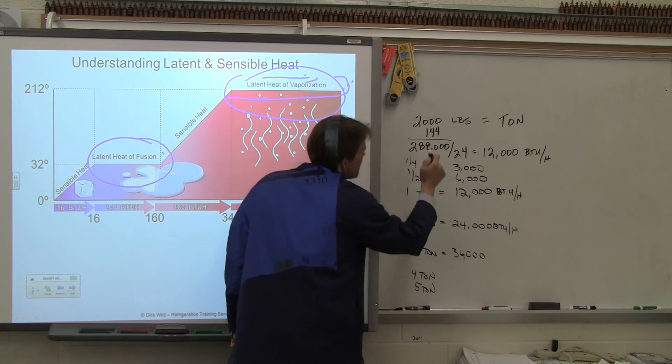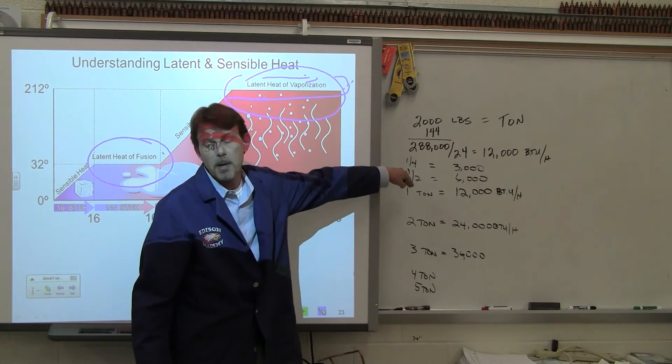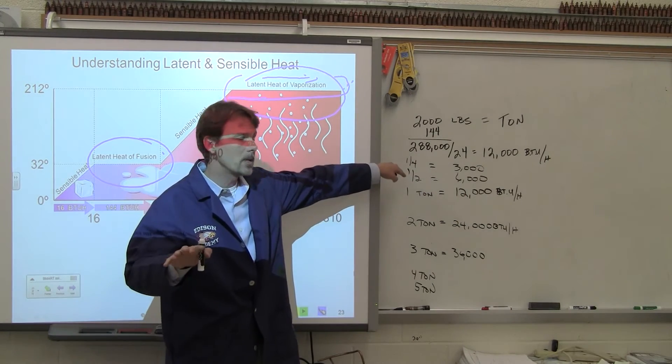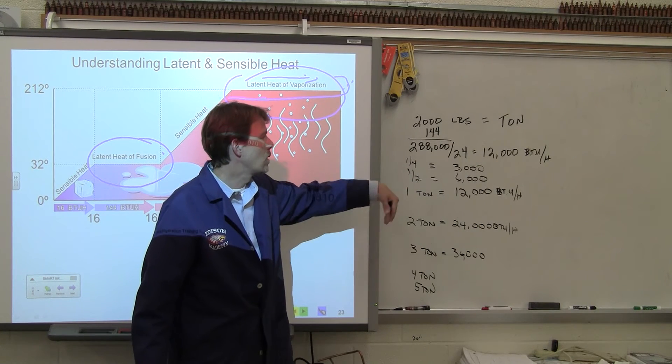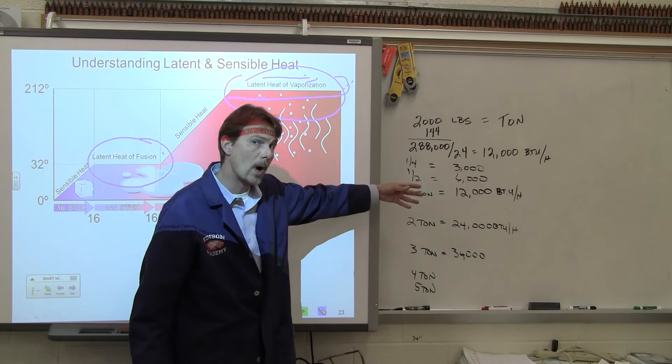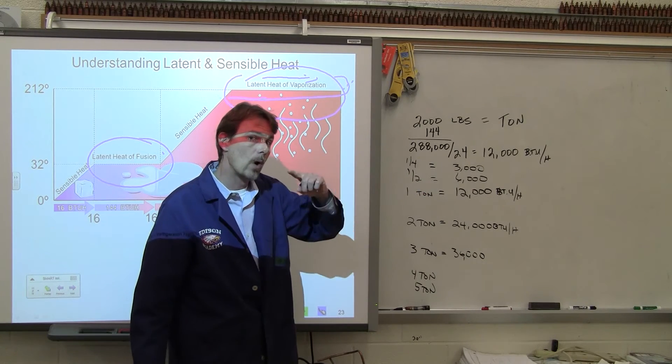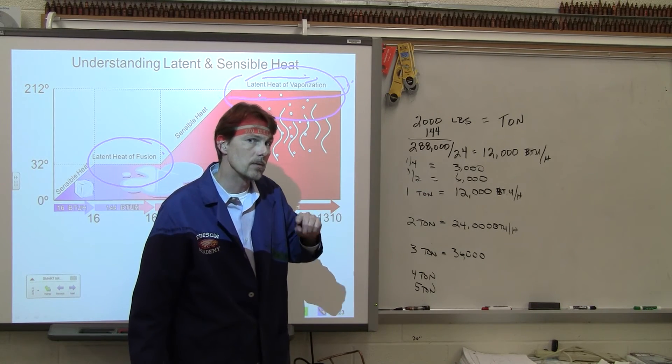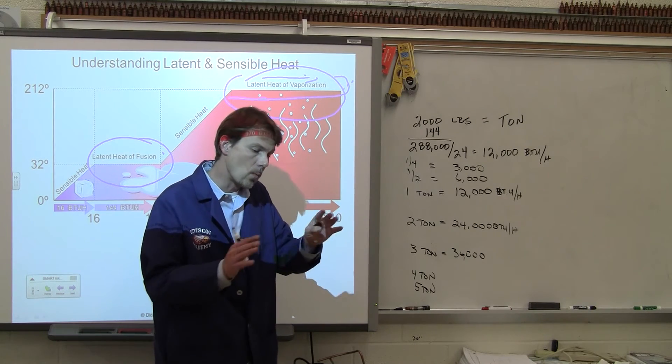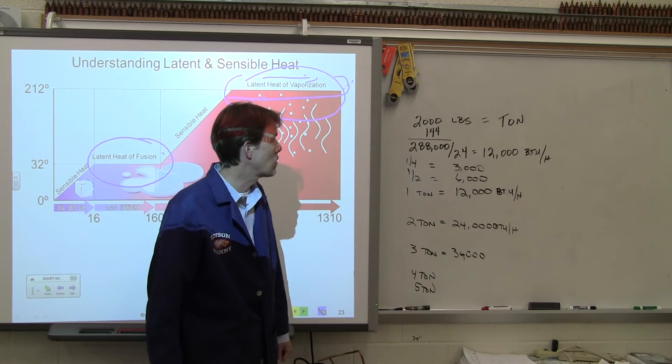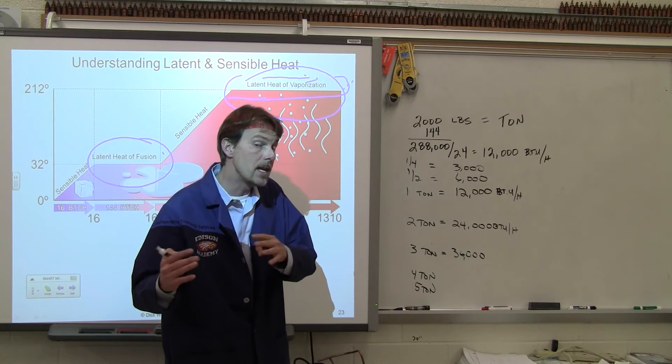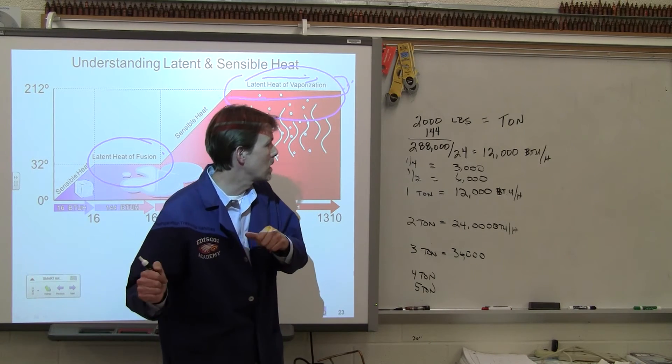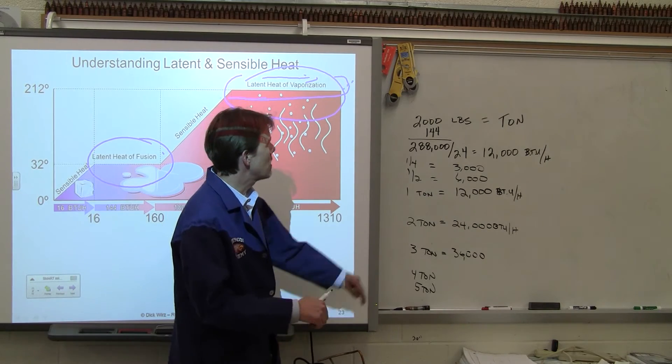And then a quarter ton is 3,000 BTUs. Usually for refrigeration, anything smaller than half or quarter, we start talking about horsepower. That's a different formula we have to do, a different calculation, because they figure out that one horsepower equals 746 watts. And then one watt, it takes 3.4 BTUs to generate one watt of electricity, or we can use one watt of electricity to generate 3.4 BTUs of heat.